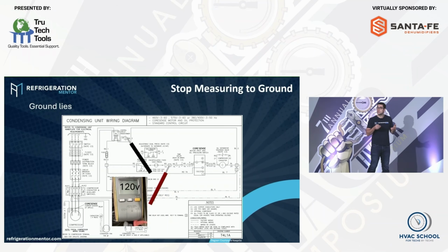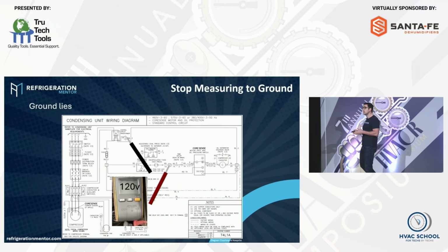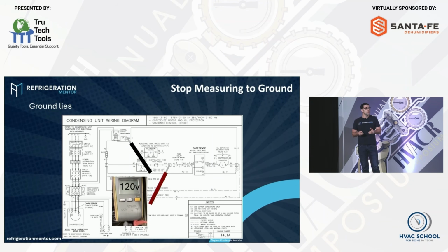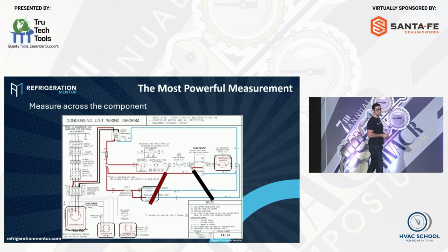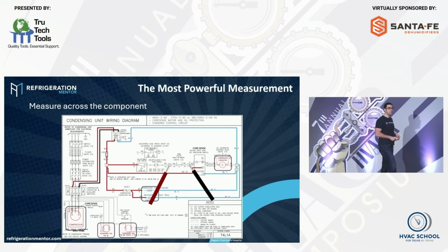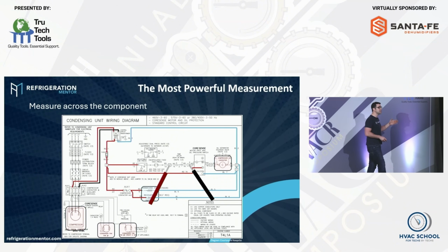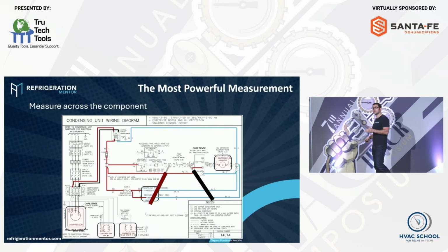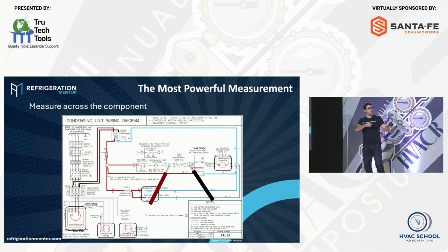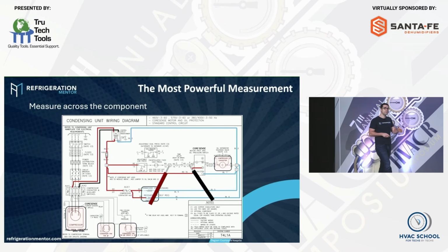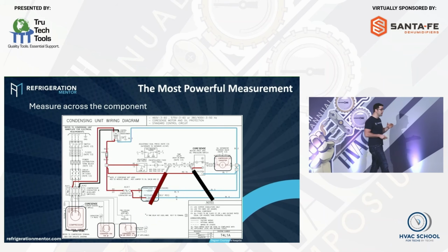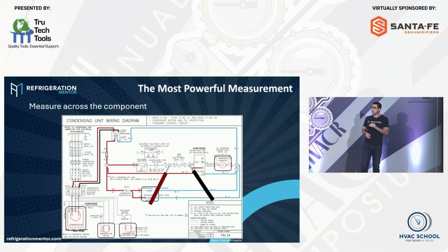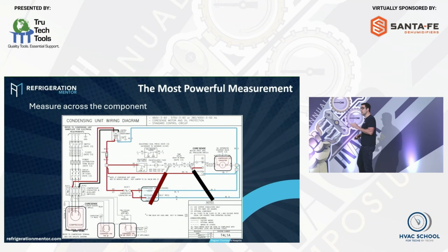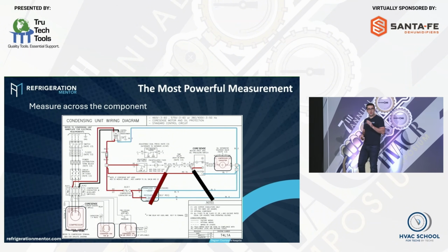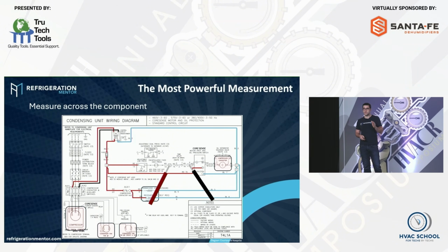And then when we get into 208, 230 volts, we really need to understand the difference than when we're going through like a 120 voltage circuit. Okay, or 24. Most powerful measurement. Measure across components. Measure across the components. Now, this is where you start to understand. I used to jump and hopscotch all over the place. There is going to be something on steps that I'm going to talk about, a strategy for you. Every time you electrically troubleshoot, it doesn't matter if there's 1,000 points or if there's 10 points, you have to have a strategy every time. And when you understand that strategy, you're going to learn faster, you're going to troubleshoot quicker.